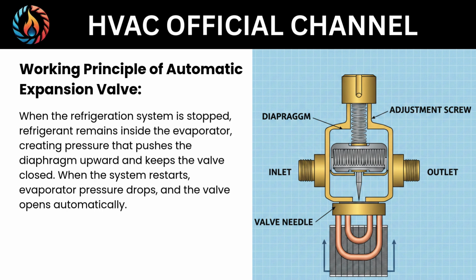When the refrigeration system is stopped, refrigerant remains inside the evaporator, creating pressure that pushes the diaphragm upward and keeps the valve closed. When the system restarts, evaporator pressure drops and the valve opens automatically.